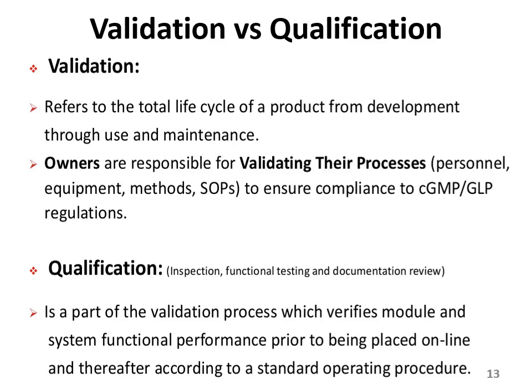Now, the qualification. Qualification, if you can see, I have written a bit detail of the qualification. That is, what is included in qualification is the inspection, functional testing, and documentation review. Okay, and if I define it, this is a part of the validation process, which verifies module and system functional performance prior to being placed online.